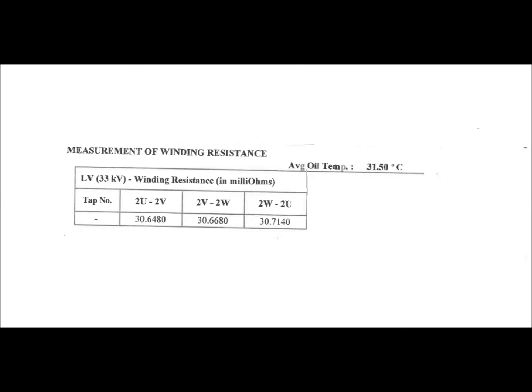The test result for each phase of the delta winding transformer is shown in this diagram. The measured resistance between 2U and 2V is 30.6480 milliohm, between 2V and 2W is 30.6680, and between 2W and 2U is 30.7140. Here the measured resistance is independent of the changing of the tap in the primary winding.